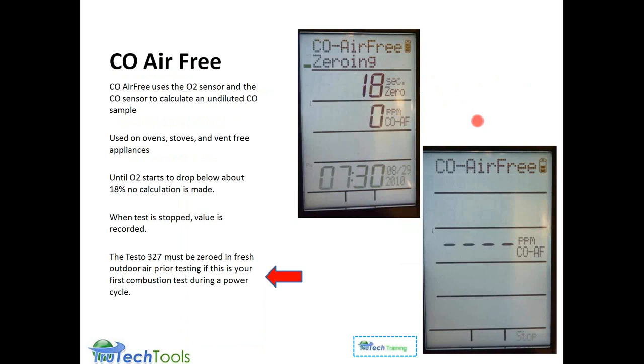The CO air-free parameter, again, is used in oven stoves and pretty much in vent-free appliances. It's actually a calculation used with the CO and the oxygen sensor, and it won't start calculating until it drops below about 18% oxygen. So if you're trying to measure CO air-free and you see dashes, you're really not in a combustion zone. You're so diluted with excess air, with excess oxygen, it's above 18%, that there's no calculation possible.